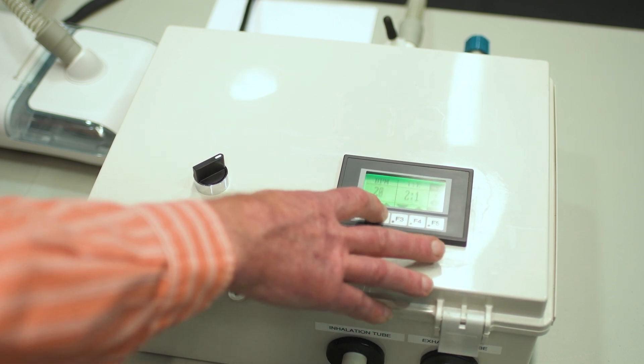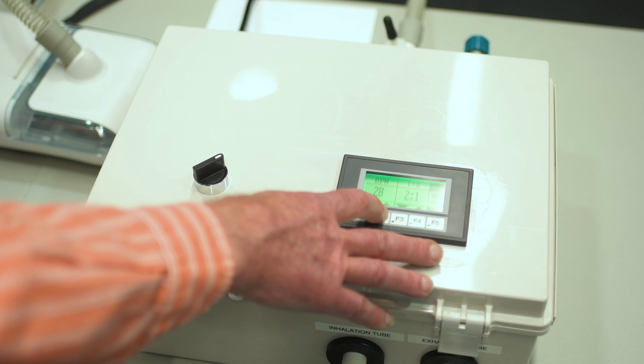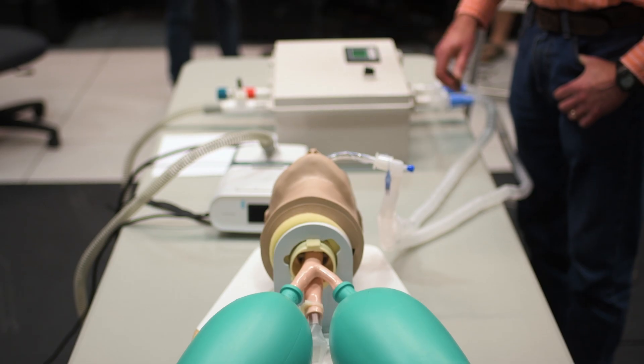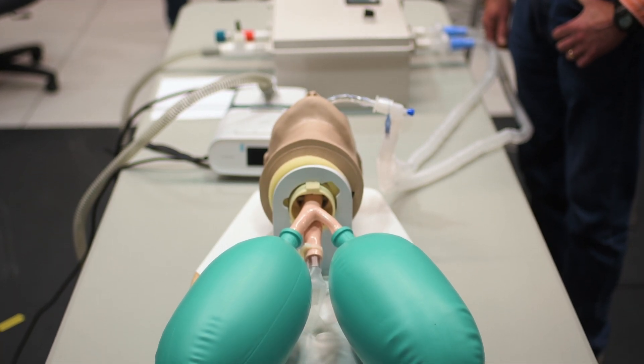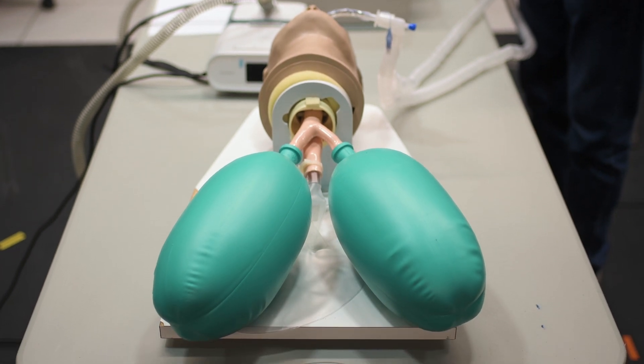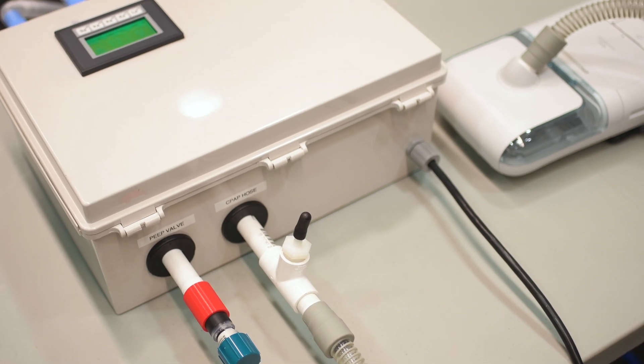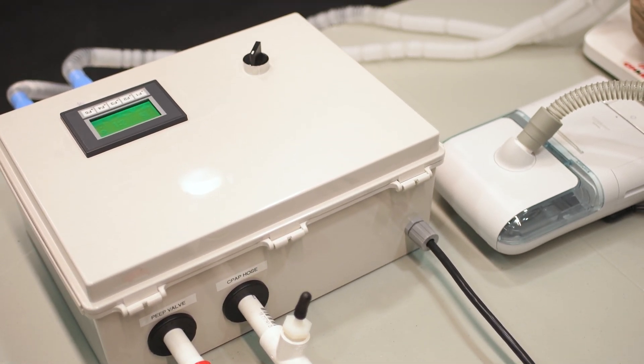It's familiar for the physicians, similar to how they might change control settings on a ventilator. You need to be able to put that pressure in and relieve that pressure on a regular pattern, and be able to control how long you're putting it in and how long you're taking it out. The concept was to take the CPAP and let that be the motor — the driver — the thing that produces the moisturized, pressurized air, and feed that into a sequence of valves to open the valve up to allow the air from the CPAP to go into the lungs and pressurize them.